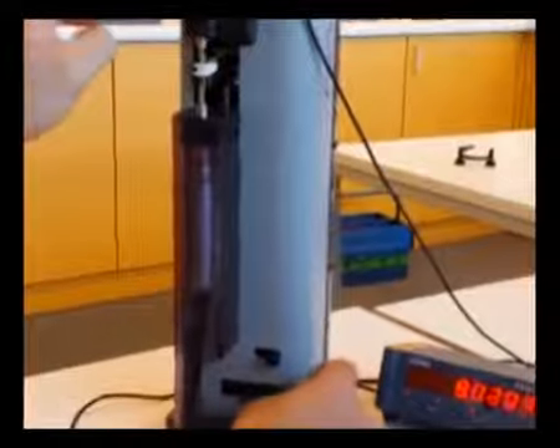Once I have my step, I can send it to the gauge, to the computer, which will tell me the next point to reach. So I go to 5.1 millimeter, then to 10.1 millimeter, and here we are finished with the steps for the total range error of the gauge.